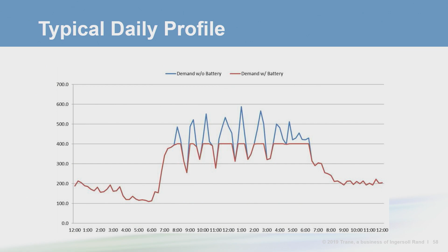Whereas ice storage is typically used for much longer durations and will not ramp up and down as quickly as batteries, it makes sense in a building to first deal with shifting the massive cooling load. Reduce that 20 to 40% of the peak load with thermal storage, then smooth out the jaggedness of the reduced peak load with batteries. In this way, batteries work synergistically with ice as a complete energy storage solution.